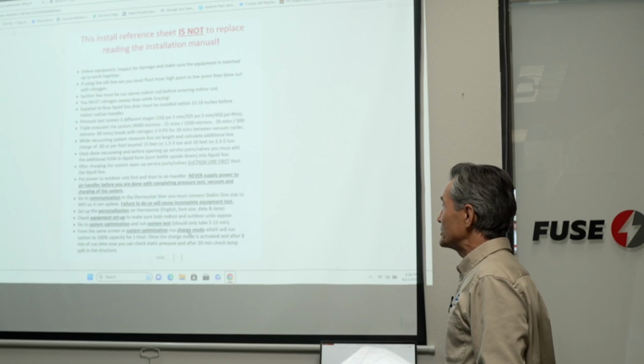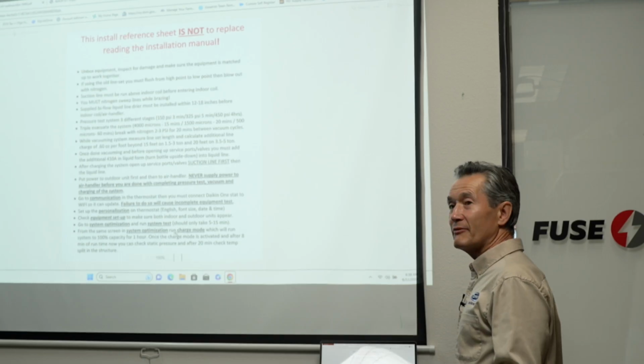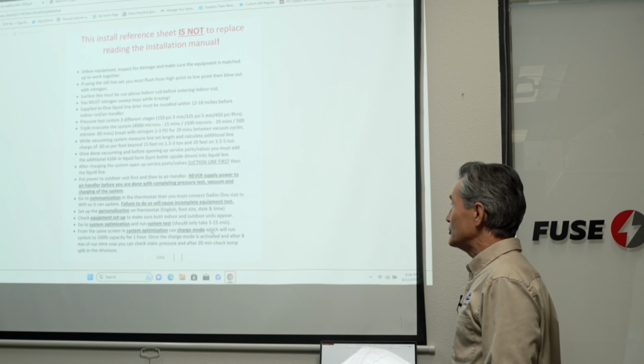And from system optimization, if you haven't charged it before, it'll give you time to charge. You can do that. And run the system, 100% capacity, says in here, for 1 hour. There is another 1 hour. You have to wait. We totally understand. It was a lot of questions. Why it takes that much time. The commissioning part sometimes takes 30% of your whole installation period.